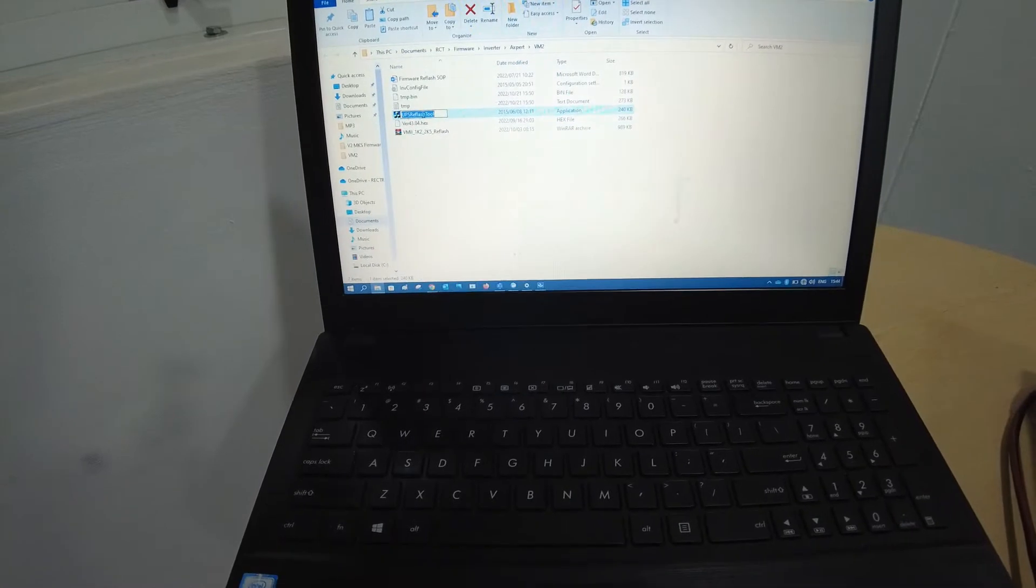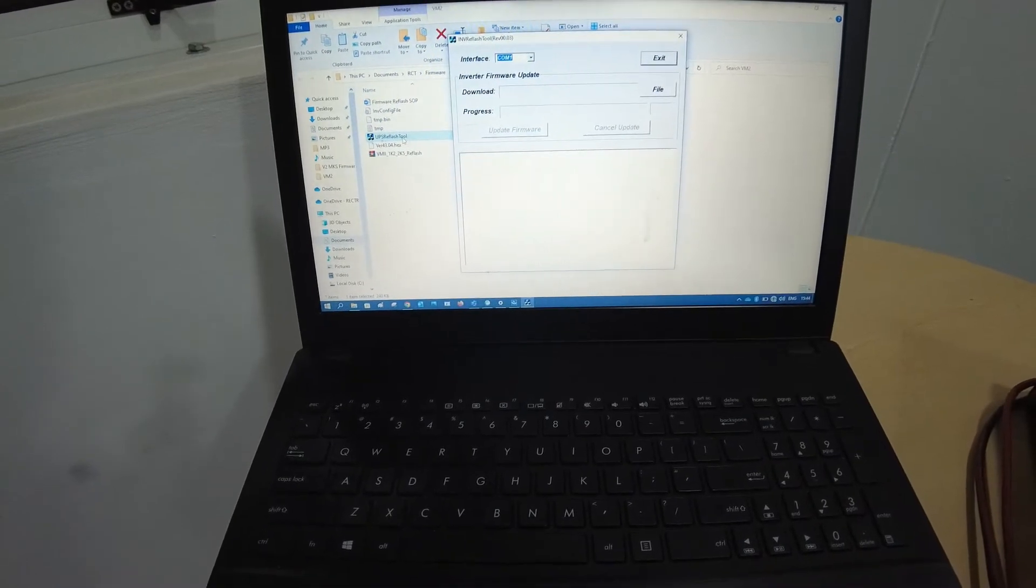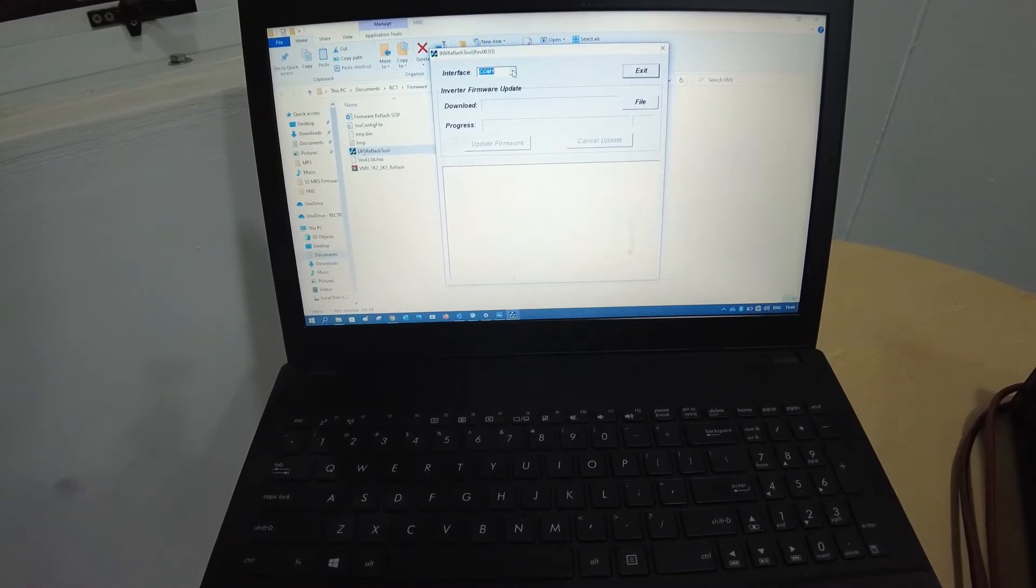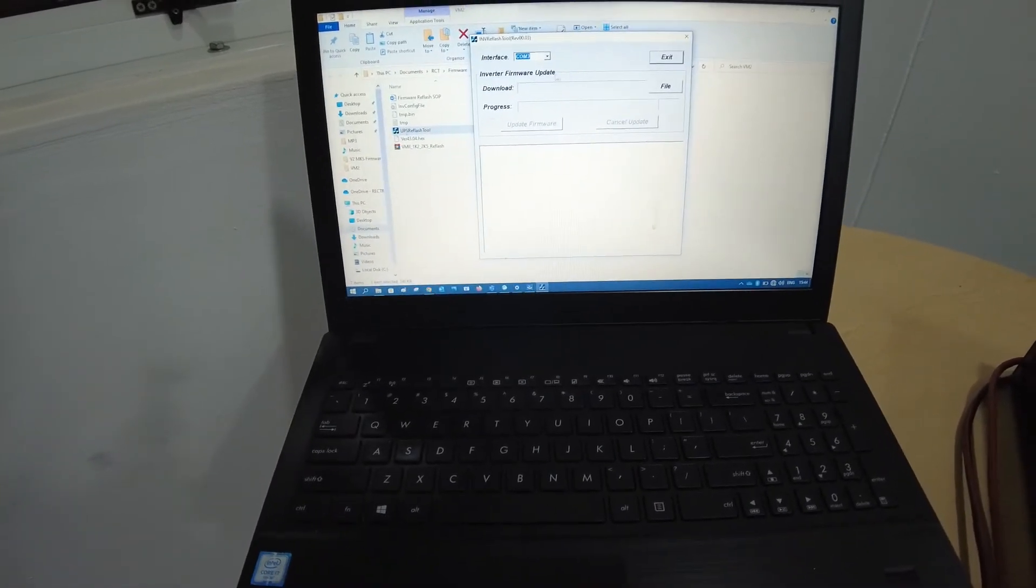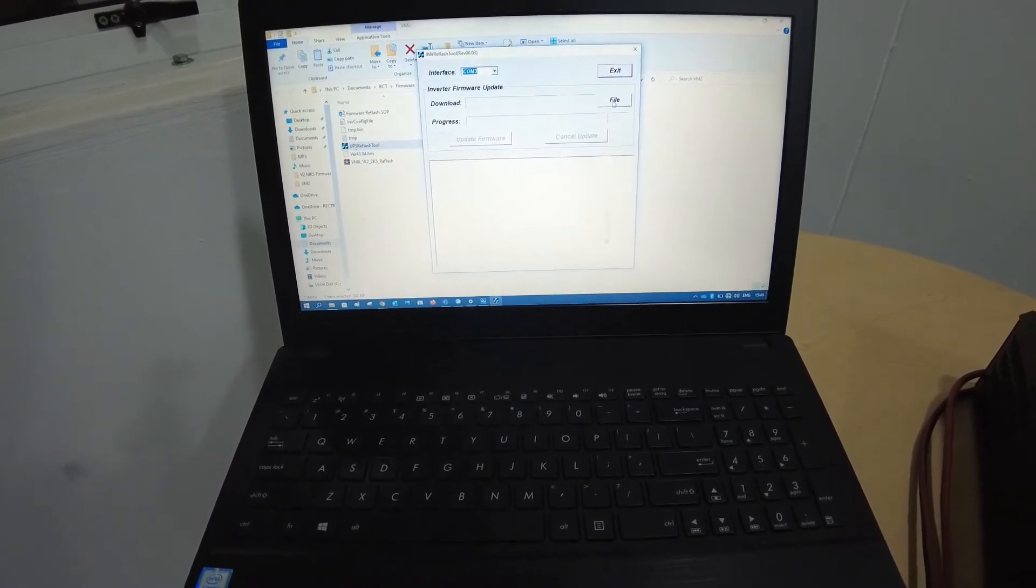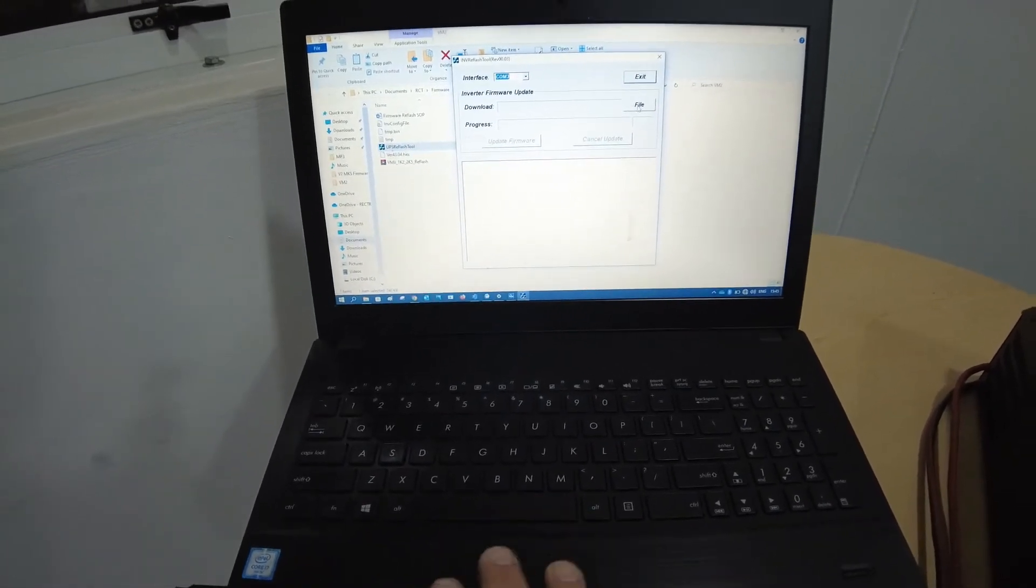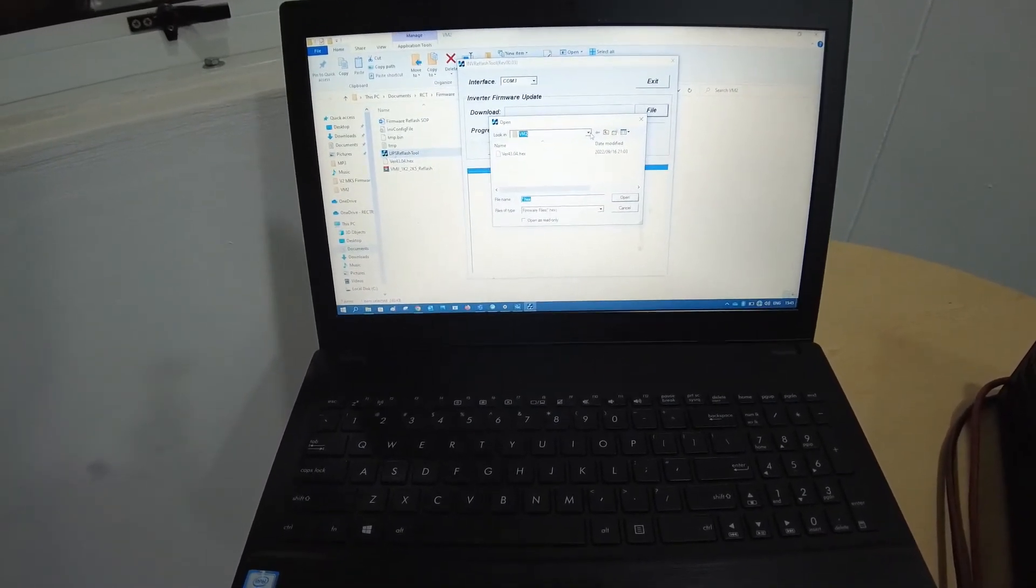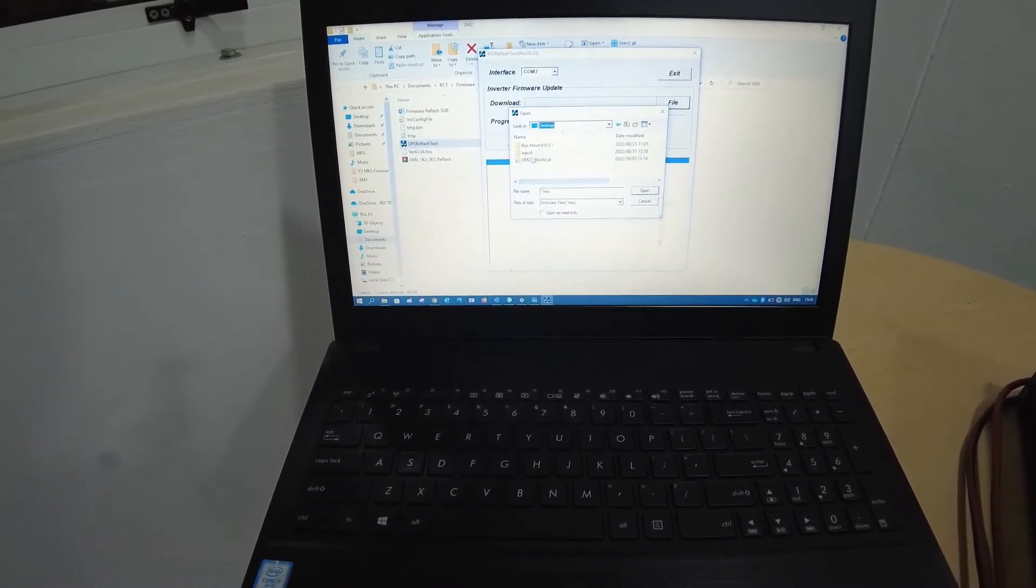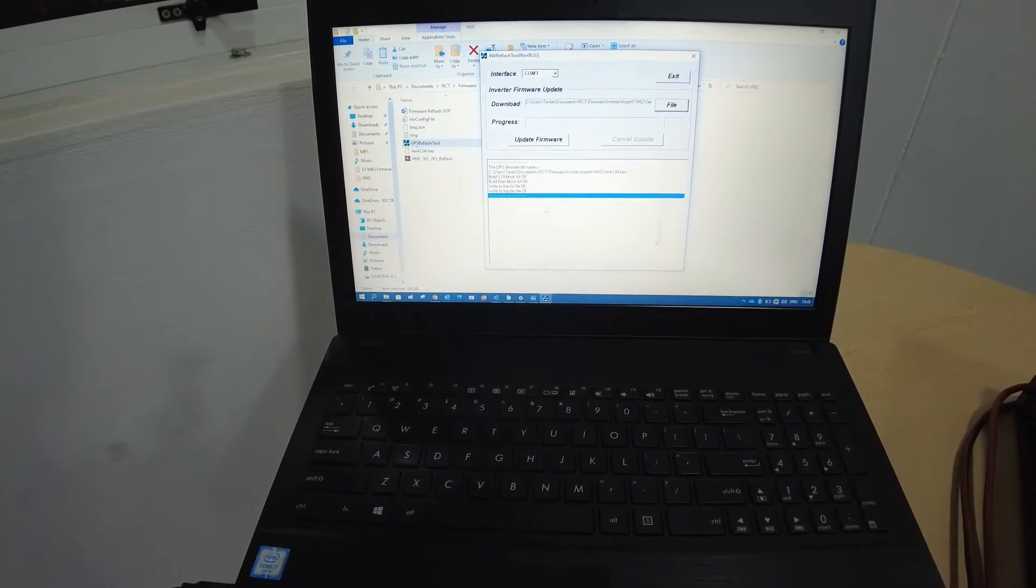Looking at the software you will need to find this UPS reflash tool. Double click that. As you can see it automatically detects COM1. As I mentioned we need to change it to what you found in device manager which is COM3. Another critical place is you need to specify where the file is at. In this case I've saved the files onto my desktop. Click file, desktop VM2, and then you can select the file. It's ready to go.